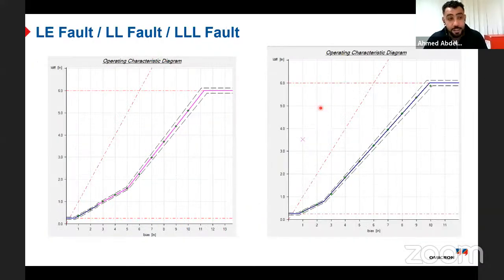And at the end, you test the characteristic and you see now the differential characteristic for single phase fault and the differential characteristic for phase to phase and 3-phase fault. You can see here, the color is pink. This is due to the non-combined characteristic of the ABB relay.